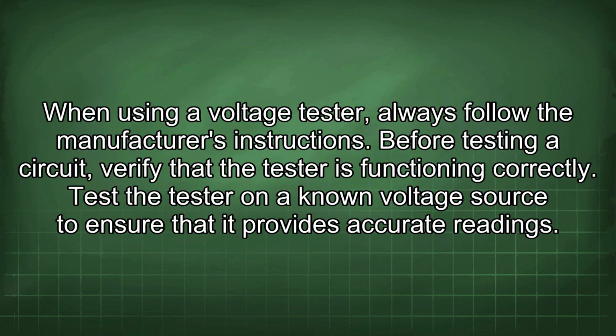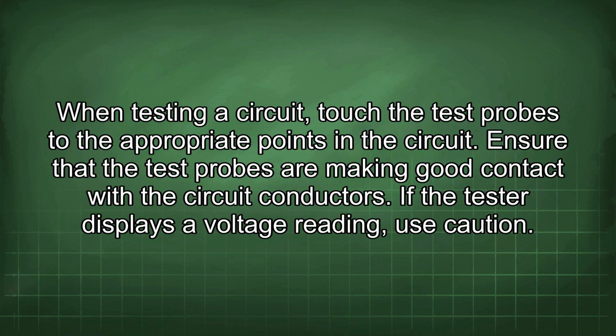When using a voltage tester, always follow the manufacturer's instructions. Before testing a circuit, verify that the tester is functioning correctly. Test the tester on a known voltage source to ensure that it provides accurate readings. When testing a circuit, touch the test probes to the appropriate points in the circuit. Ensure that the test probes are making good contact with the circuit conductors.